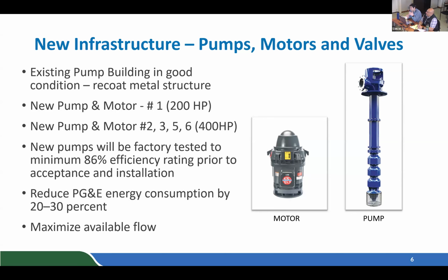And you may be asking, what does 20 to 30% look like? I took a look at the numbers last week. Over the last 5 years, this one pump station has an average of $1 million per month in electrical PG&E charges. So our monthly charges can be expected to drop to about $700,000, so $300,000 a monthly savings in PG&E's electrical charges due to replacing the pumps and switching over to VFD drives.